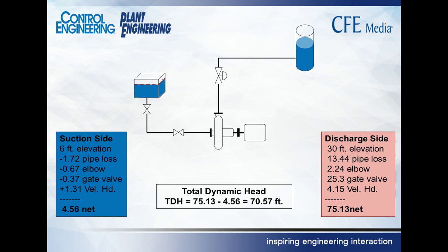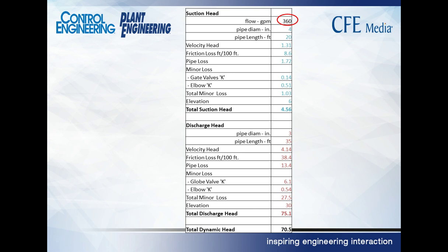Now, when I did those calculations, everything was based on 360 gallons per minute. There was some multiplication done. There are friction constants for all the different parts. They call it a K for the different elbows, and there's a pipe loss from a pipe loss table. Those are multiplied by the flow rate of 360 gallons per minute, and I'm not going to do that on a calculator. I'm going to put that in a spreadsheet with all those formulas to calculate all the losses and just total them up. 360 gallons per minute at the top, 70.5 feet of total dynamic head at the bottom.